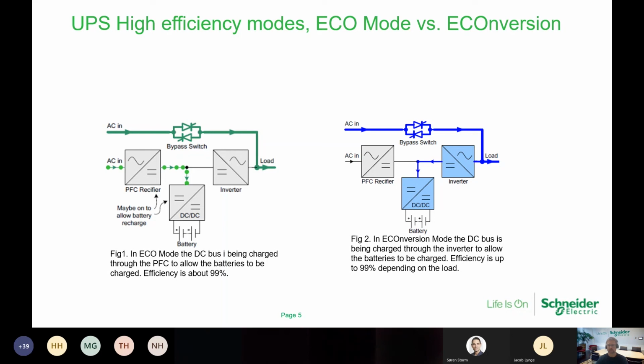The difference between eco mode and e-conversion mode is that the inverter is off in eco mode, whereas it's on in e-conversion mode. In e-conversion mode, the inverter is able to run in parallel with the bypass source, supplying the load and delivering an input power factor close to unity. Another thing in e-conversion mode is that it is possible to transfer back to inverter operation very fast compared to eco mode, if required. So keeping the inverter on in e-conversion mode has a small impact on the efficiency.